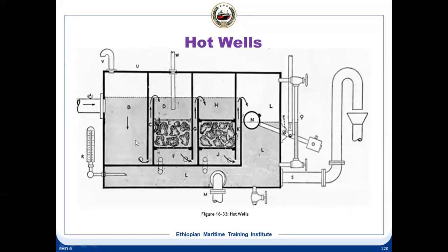So any oil that is coming in has to go through before it finally reaches the feed pump suction. For any oil to reach the feed pump suction, firstly the hot well has to be practically empty. Oil will normally tend to always float at the top of the water, and since it floats, if it tries to go past this filter, it will get trapped at this filter. So we are supposed to skim off any floating oil that we see in this chamber.